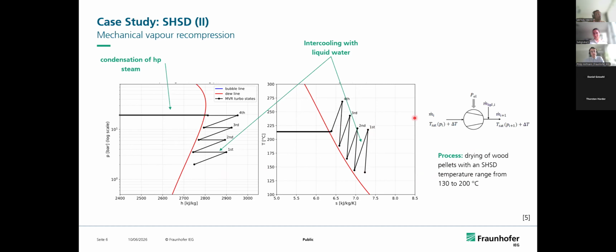We have relevant superheating in all stages, although only a small pressure increase, and therefore liquid intercooling after each stage, or in some cases with blowers even during compression, is considered. This model was used to calculate all the COPs and efficiencies in combination with the mass and energy balance superheated steam drying chamber model.